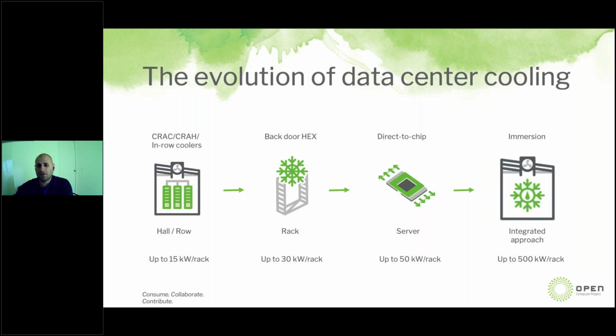Legacy air-cooled solutions were based on CRAH or row-level cooling, and had issues with high energy consumption, limited capacity per rack, noise, and limitations for high performance processors. After that, rear door heat exchangers save energy by making them smaller. The next one is on-chip cooling, which resolves the chip problem, but 40% of server heat must still be removed by air, and a leak can cause catastrophic failure.